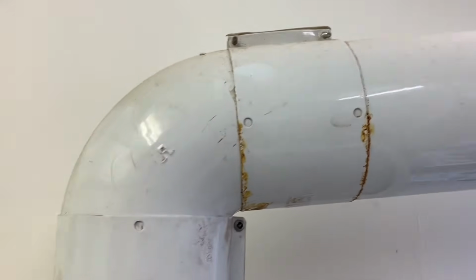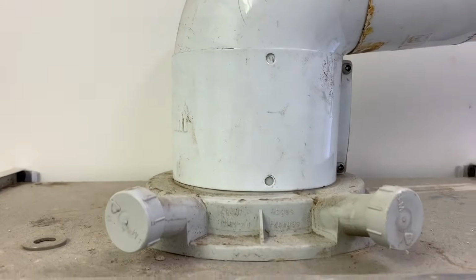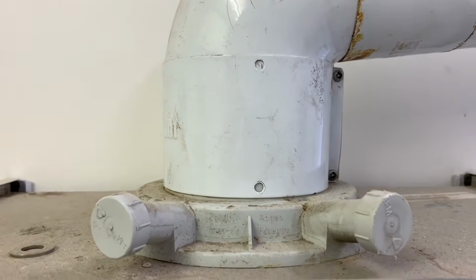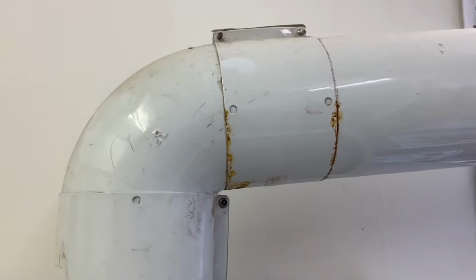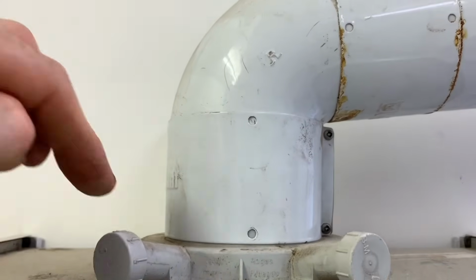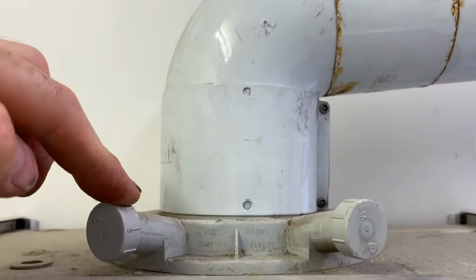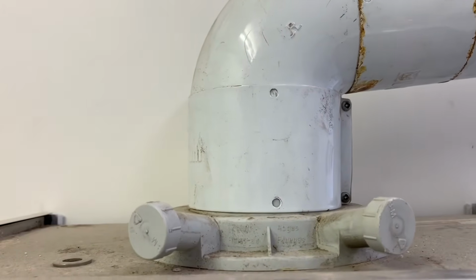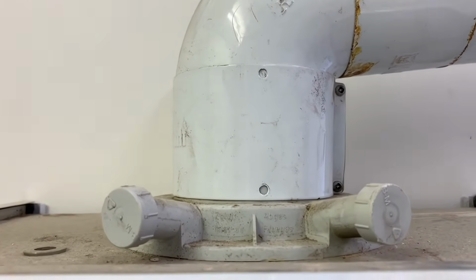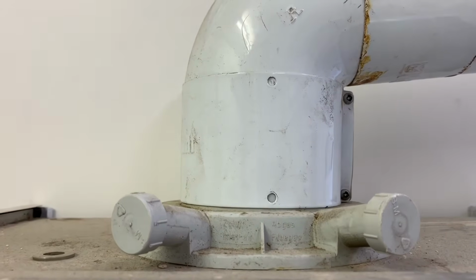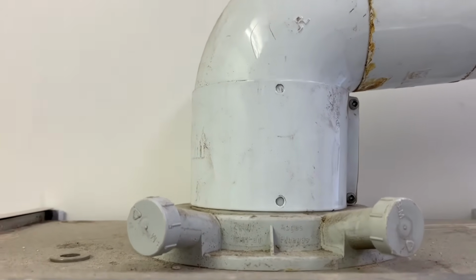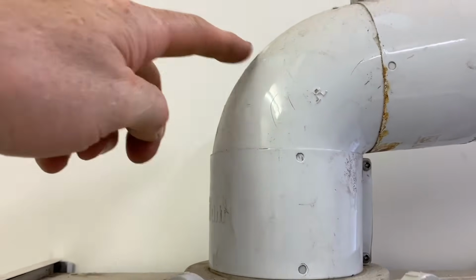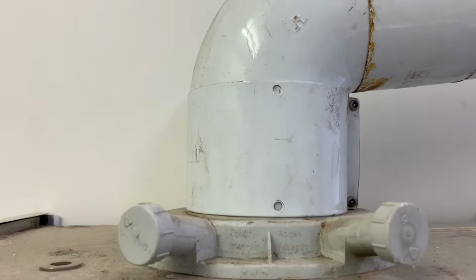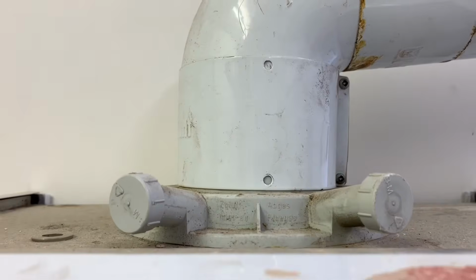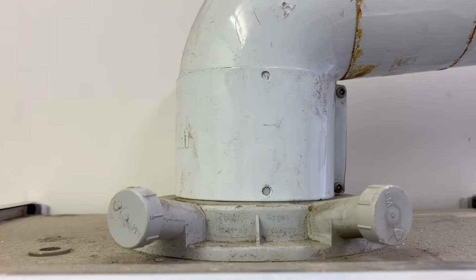Okay, so that is the top of the boiler. Basically that's all there is. It's the flue turret, the analyzer test points, and the flue itself. And again, this can flue pretty much anywhere because the test points always stay at the front, which is a really good idea on any boiler, that the test point stays where it is, which allows you to do 360 with the flue. When they put them on the actual elbows up here, it restricts you when they're on the side. Okay, so let's get this front cover off and let's have a look inside.